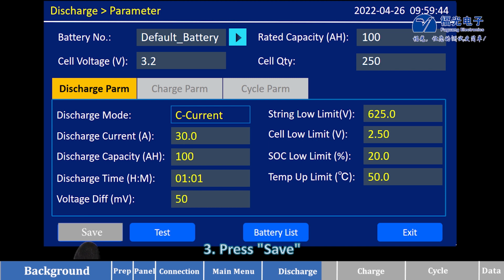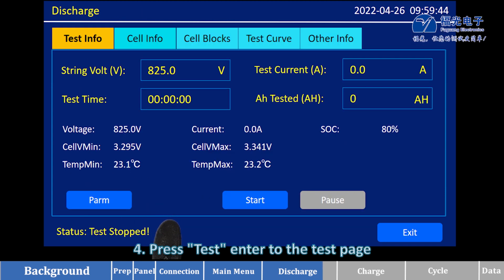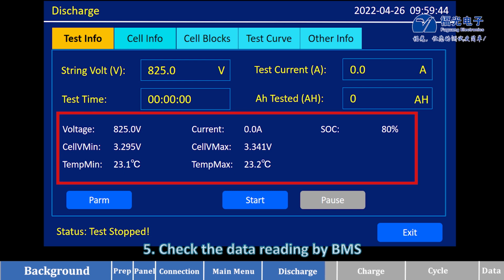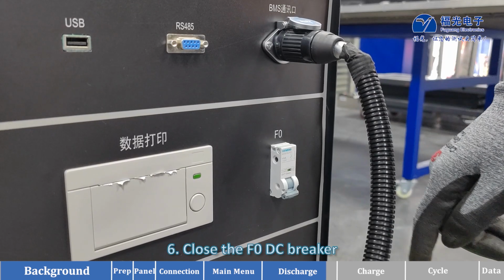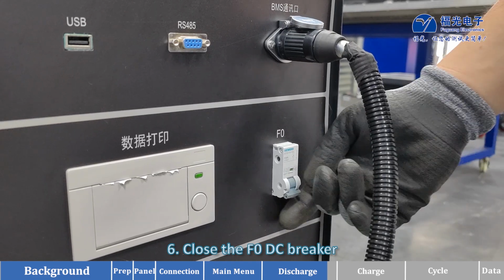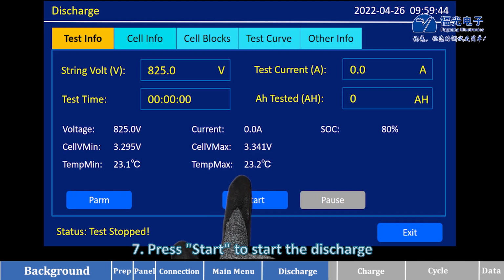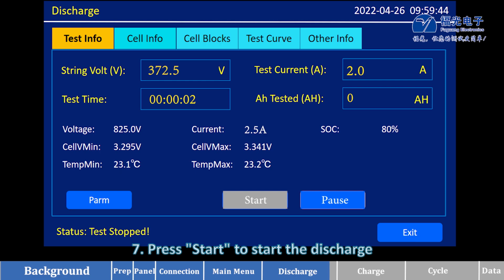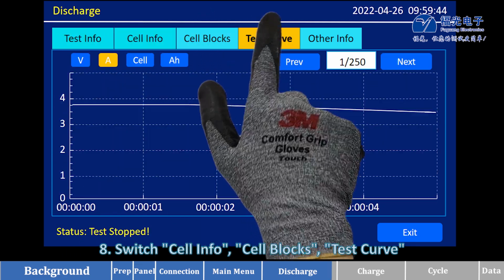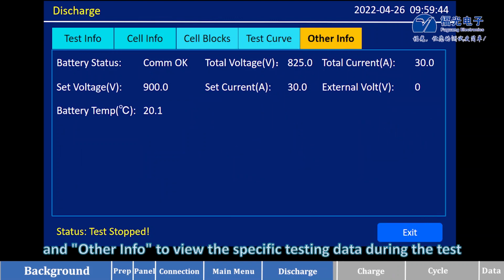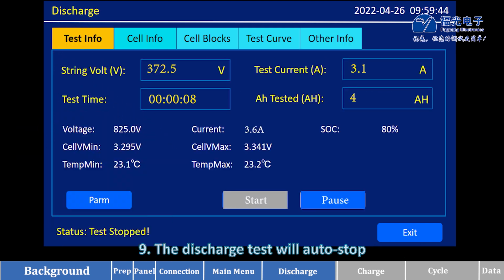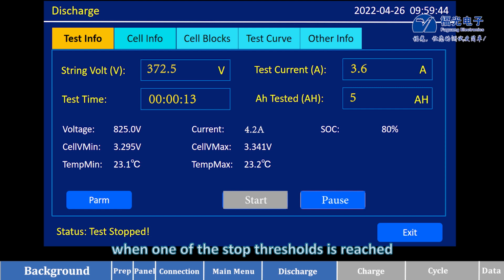Third, press save. Fourth, press test enter to the test page. Fifth, check the data reading by BMS. Sixth, close the F0 DC breaker. Seventh, press start to start the discharge. Eighth, switch cell info, cell blocks, test curve, and other info to view the specific testing data during the test. Ninth, the discharge test will auto-stop when one of the stop thresholds is reached.